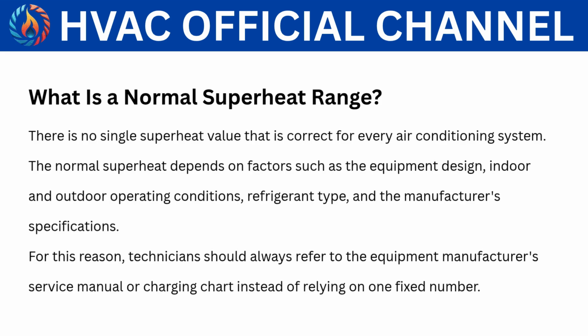What is a normal superheat range? There is no single superheat value that is correct for every air conditioning system. The normal superheat depends on factors such as the equipment design, indoor and outdoor operating conditions, refrigerant type, and the manufacturer's specifications. For this reason, technicians should always refer to the equipment manufacturer's service manual or charging chart, instead of relying on one fixed number.